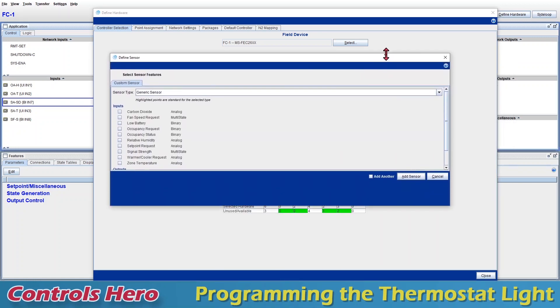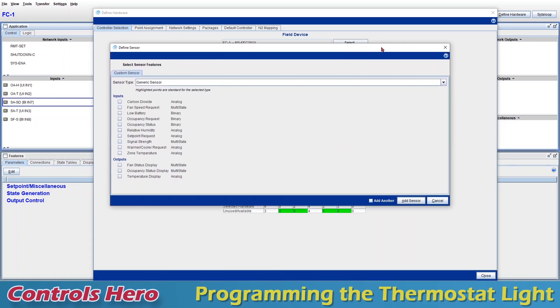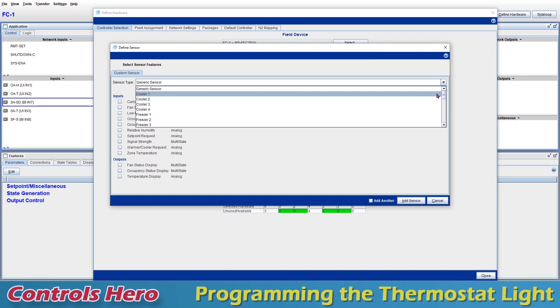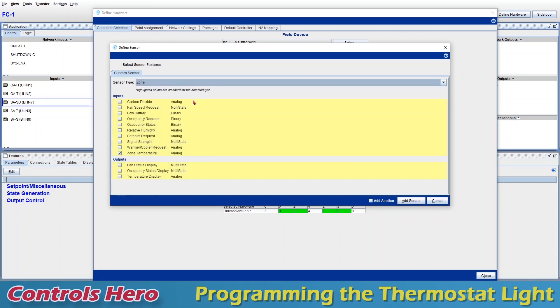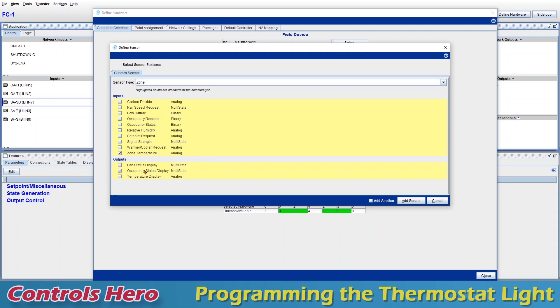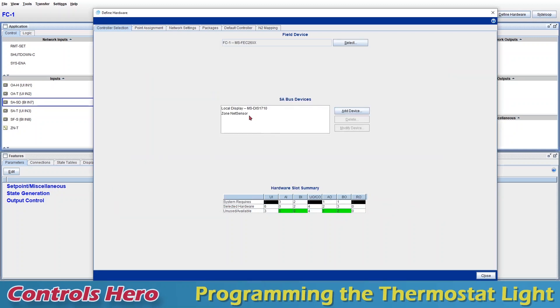We have a new window up here. I don't want a generic sensor, I want a zone sensor. Since we're only adding one, I'm just going to do zone. You can see by default it picks zone temperature. My thermostat light is going to be an output, it's going to be the occupancy status display. Why an output? That's because we're going to be commanding that point so we can turn on the light. I'm going to add the sensor.